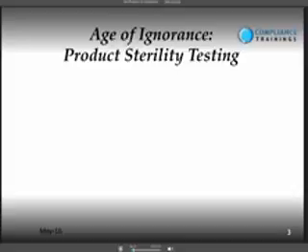Notice that the lot would have to be over 3% contaminated before the test would have even a 50% chance of catching it. To put this in perspective, a 0.1% contamination level is equal to one non-sterile unit in 1,000. But the sterility assurance level for sterile products is less than 0.0001%, or less than 1 in a million. To detect 1 in a million at a 90% confidence, we need a sample size of over 100,000 units. That's just impractical. Therefore, with any reasonable sampling plan, we can only detect gross contamination, and the test can't be used with any confidence to verify the required SAL.